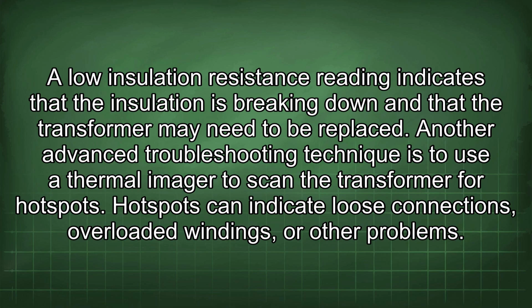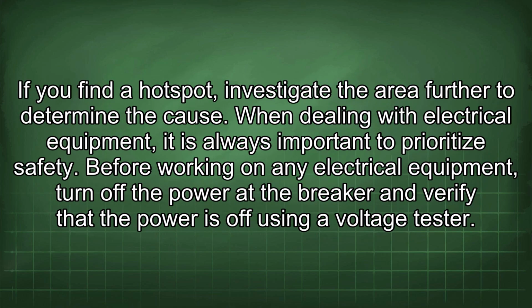to be replaced. Another advanced troubleshooting technique is to use a thermal imager to scan the transformer for hotspots. Hotspots can indicate loose connections, overloaded windings, or other problems. If you find a hotspot, investigate the area further to determine the cause.